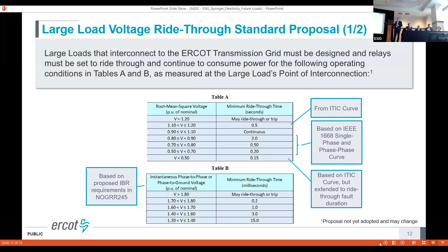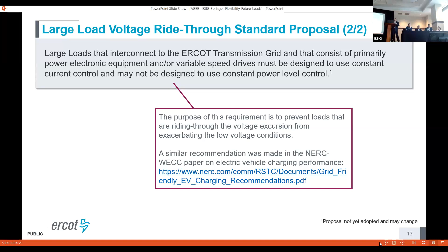And then the other piece of the proposal would be that loads that are primarily power electronics or variable speed drives would be required to use constant current control and not constant power, so that they don't draw in a bunch of excess current and exacerbate the low voltage condition. So those are proposed, but that's how we're looking at that.